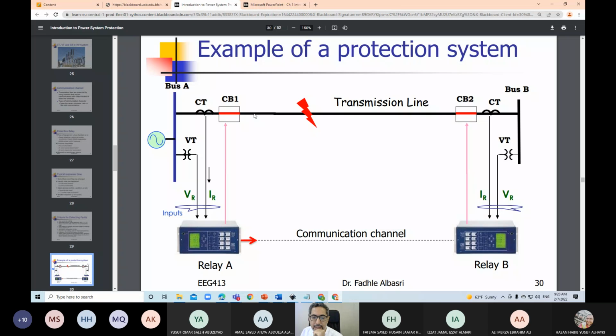So this relay, once it gives a command to this breaker, will send through the communication channel a command to the other relay telling it, I have already issued a trip signal to my breaker, and I recommend you disconnect your line, even if you did not discover this fault. So this relay, once it has received this command from the other relay, will send a command to this breaker to open breaker 2. And with this, the fault is disconnected from the two ends. So this is a protection system for a transmission line using a protective relay, current and voltage transformer, circuit breaker, and communication channel, all together in that system.